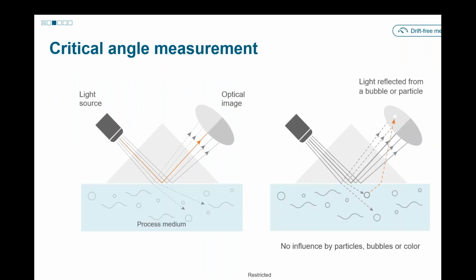So here's just sort of an overview of how that looks. One thing that's important to note is we're looking at the shadow line, the difference between the dark and the light areas. So if a bubble passes and it reflects or refracts the light slightly differently in that area of the bubble, it's going to show up as a little bright blip on the CCD, but it's not going to affect where that shadow line shows up. So you won't have any influence from that particle or bubble.